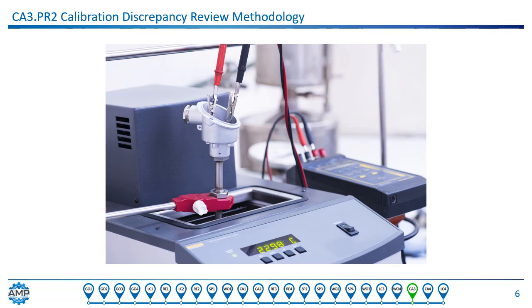This discussion about deviations is limited to how calibration interacts with product quality. When process instrumentation is out of calibration, process parameters such as temperature, pressure, vacuum, or others might operate outside of defined limits. If the condition that causes the instrument to be out of calibration is significant, the affected instrument could allow the associated process parameter to exceed process tolerance values. If this happens, product quality, purity, or strength might be adversely affected.